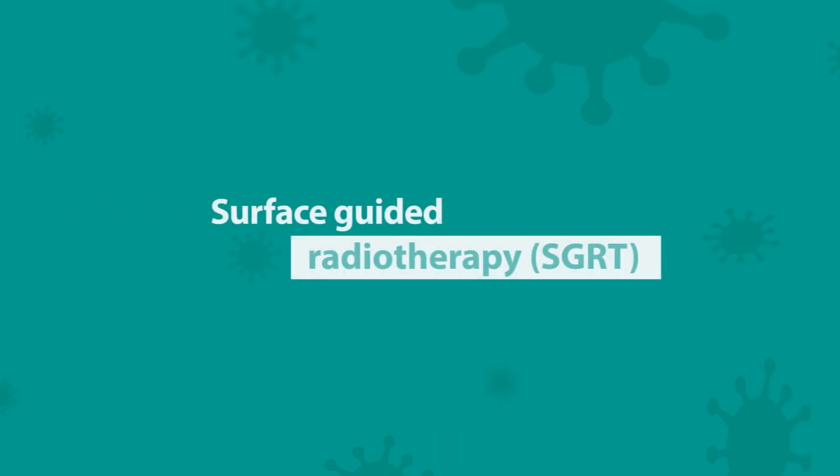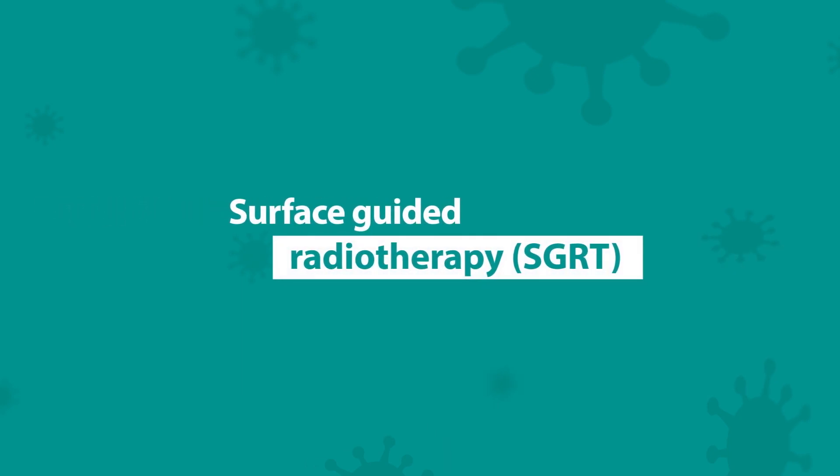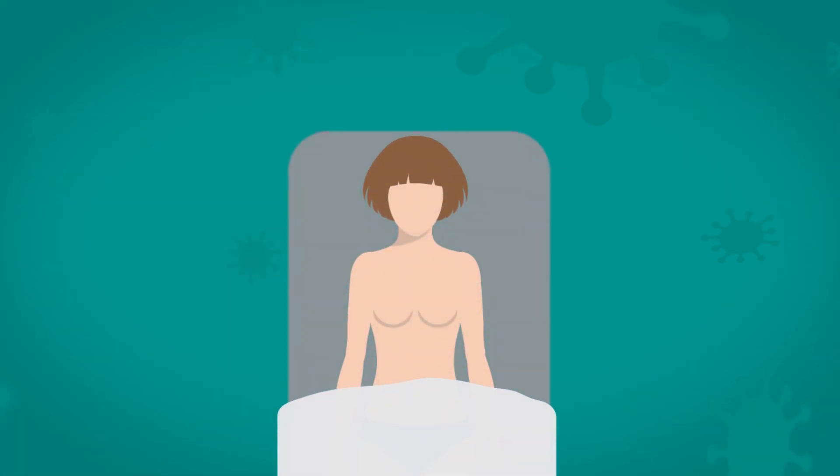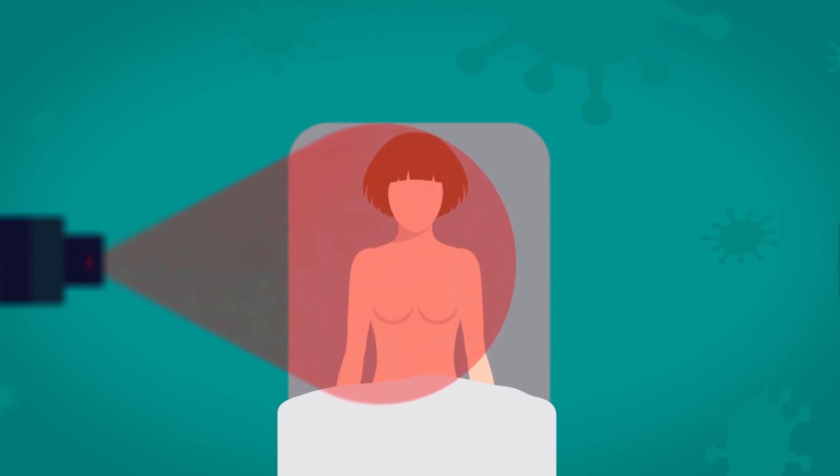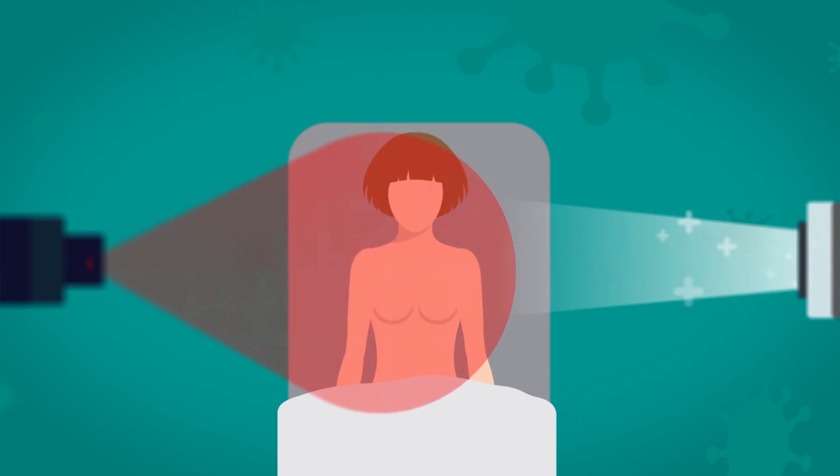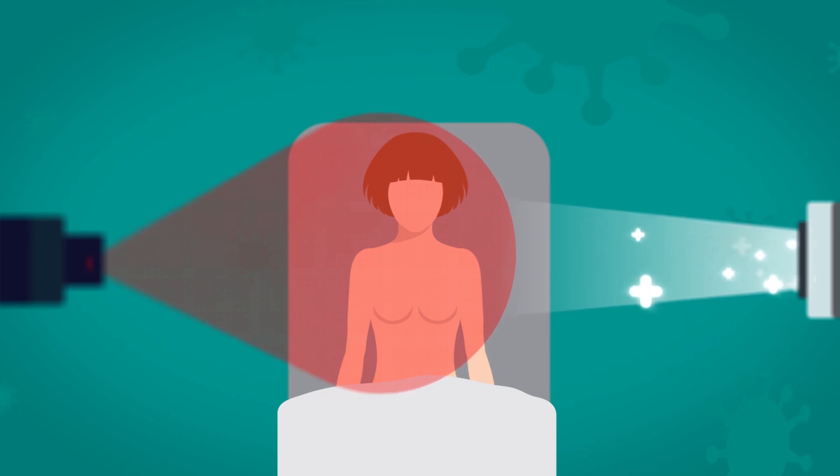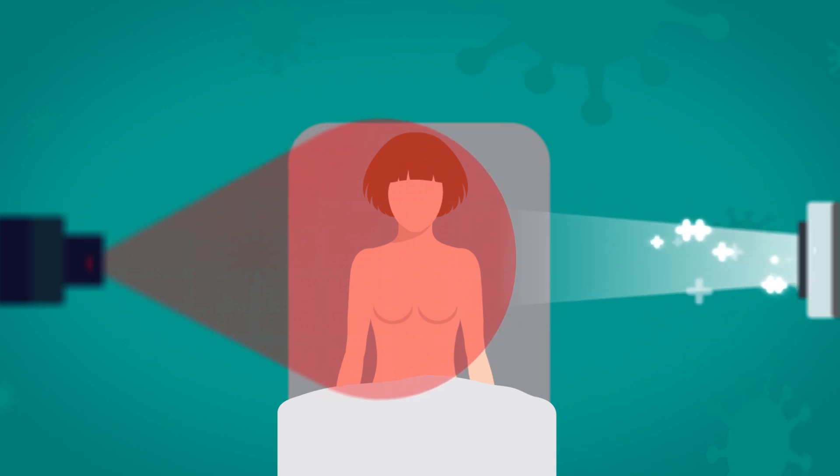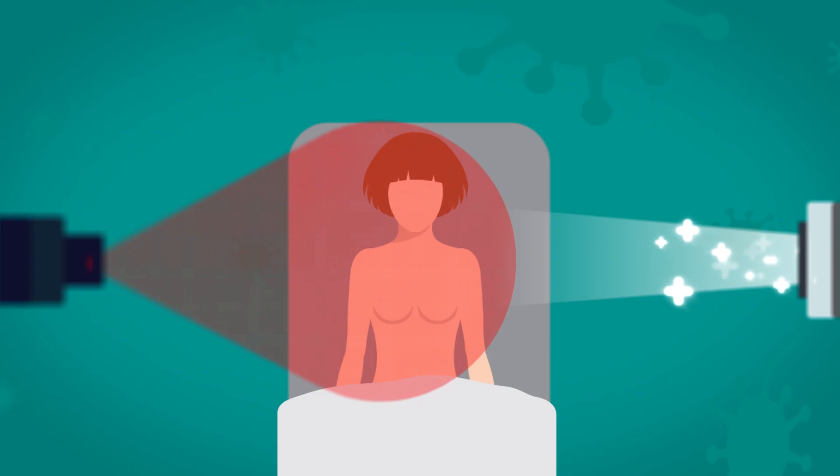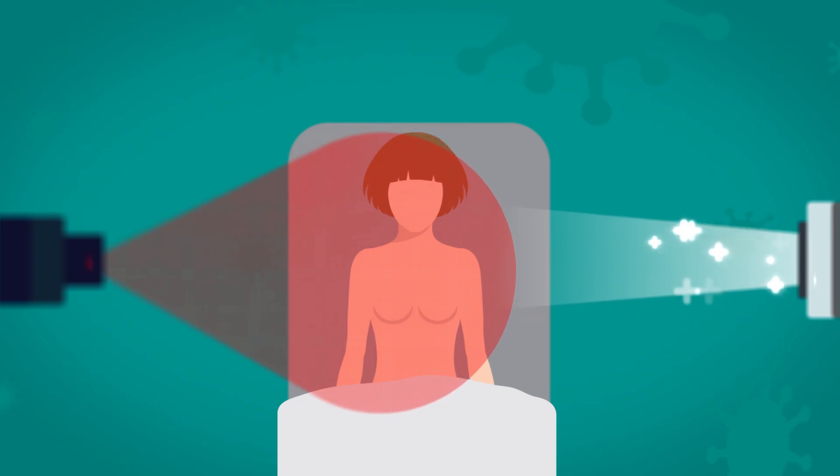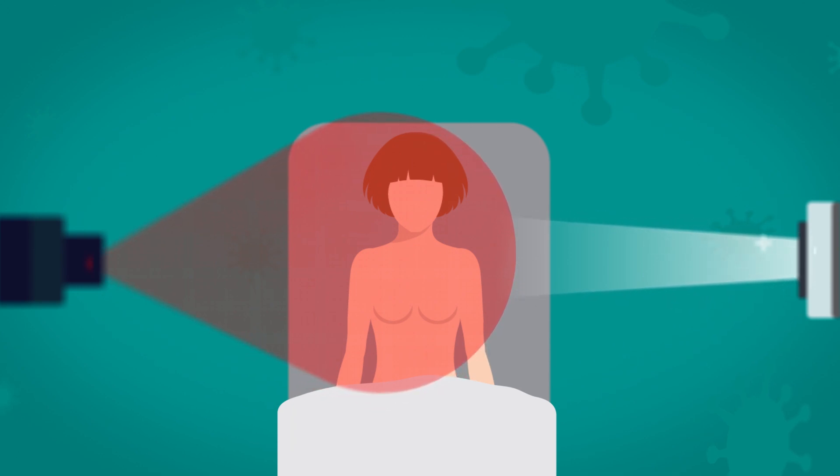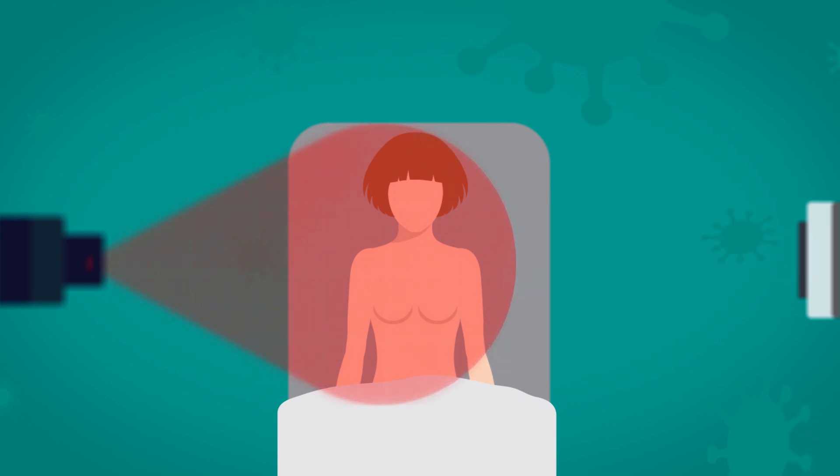Surface-guided radiotherapy. SGRT uses sophisticated 3D camera technology to accurately target treatment. It does this by continuously and accurately monitoring a patient's position during treatment, using the surface of the patient to do this. Without SGRT, people generally need tattoos to line up the beams, but SGRT can mean there's no need for permanent tattoo markers, and this can be of great psychological benefit for people who just want to get on with their lives, without a permanent reminder of their treatment.